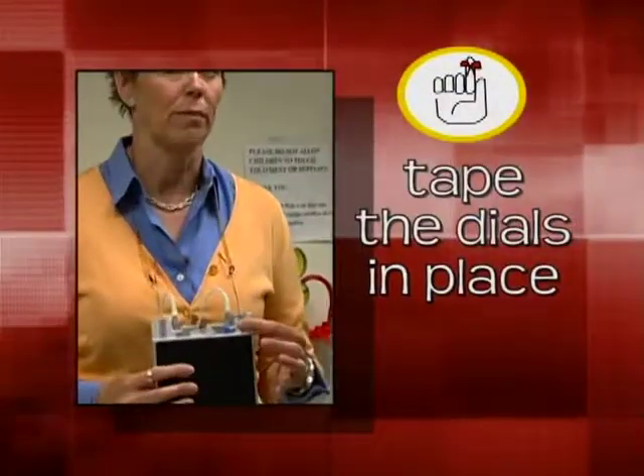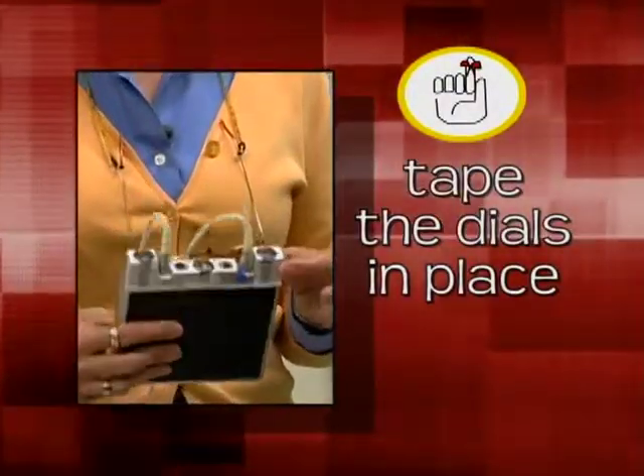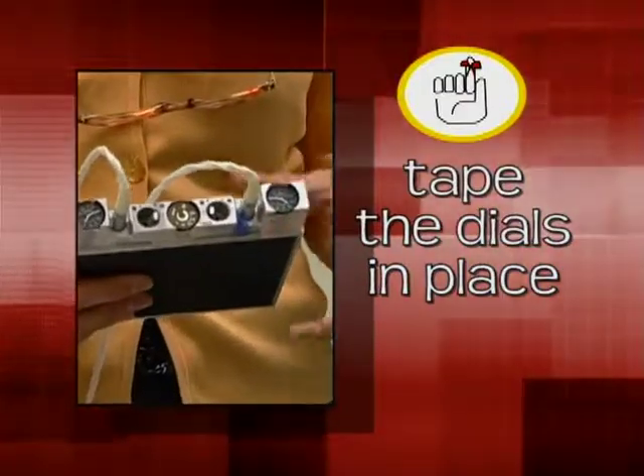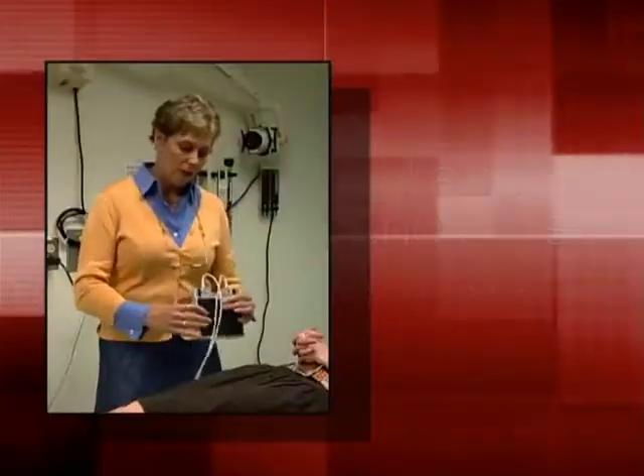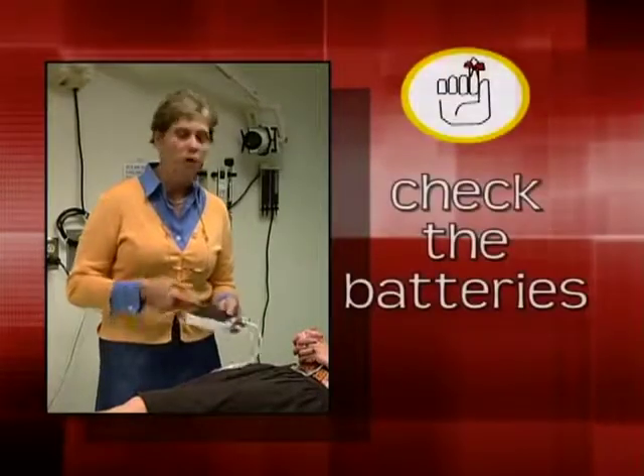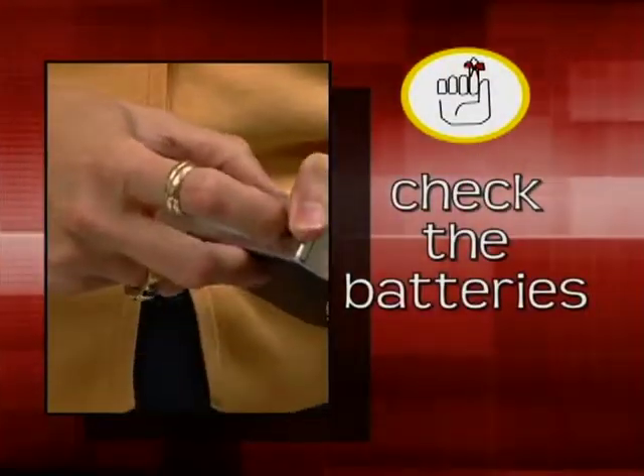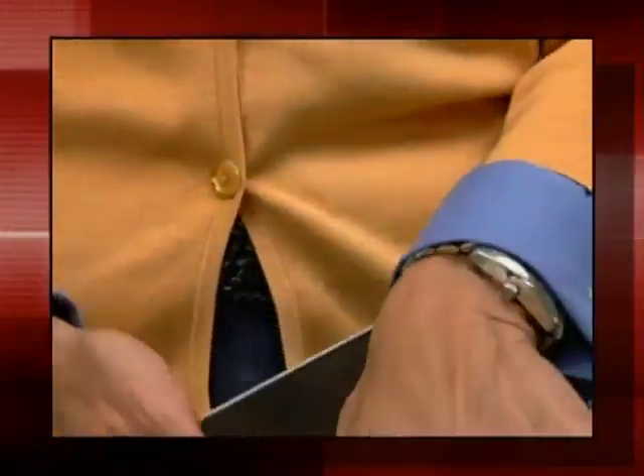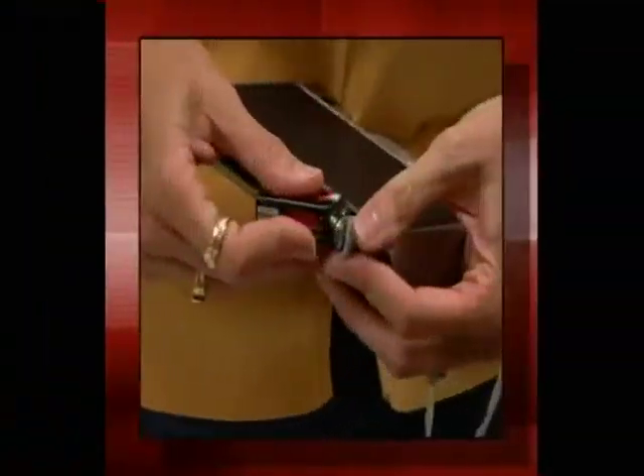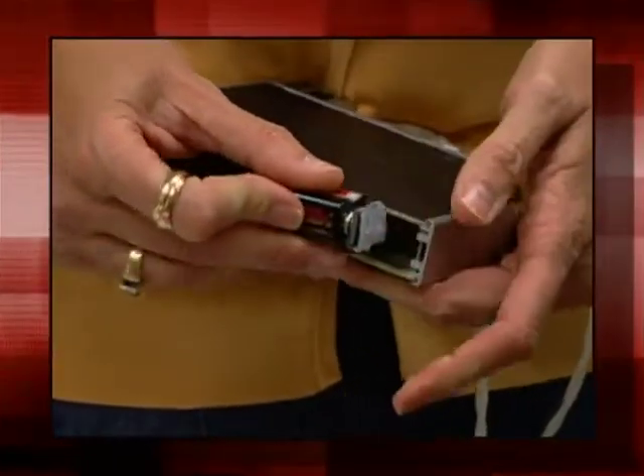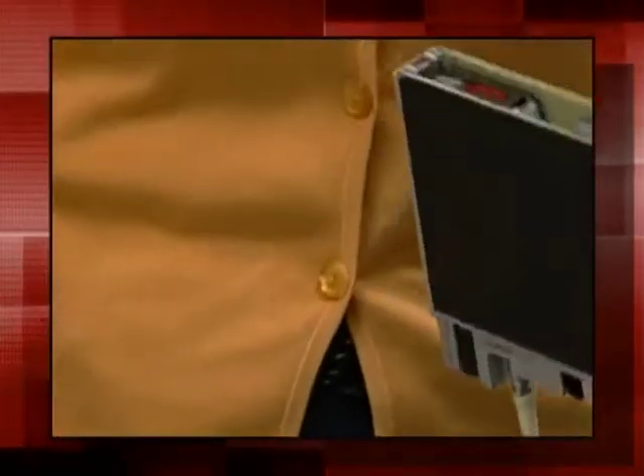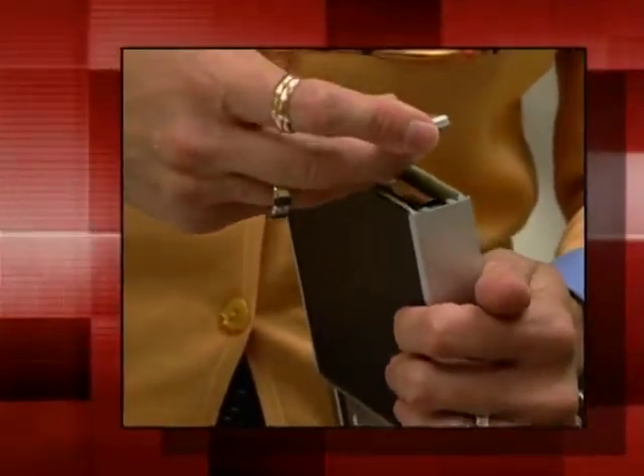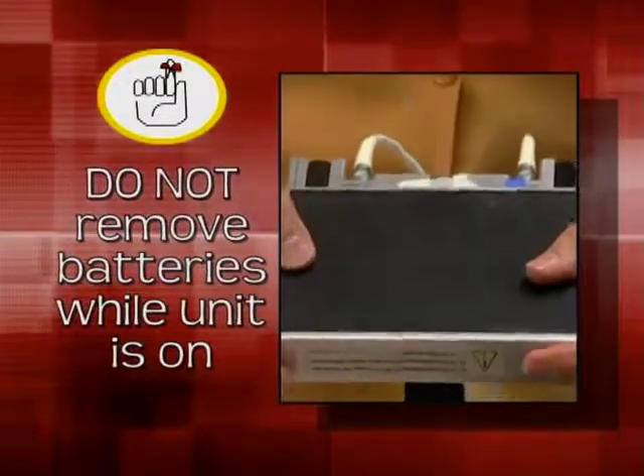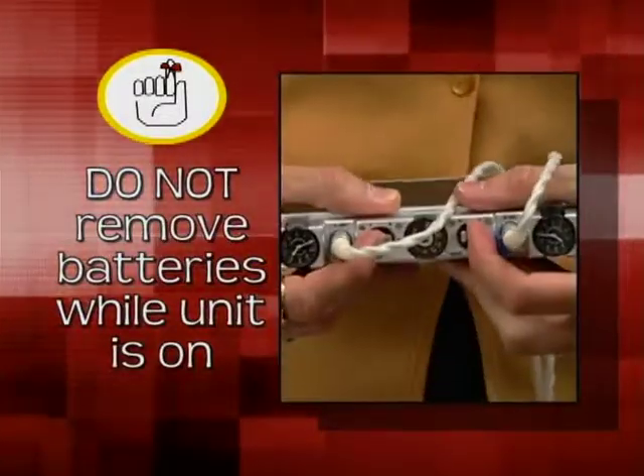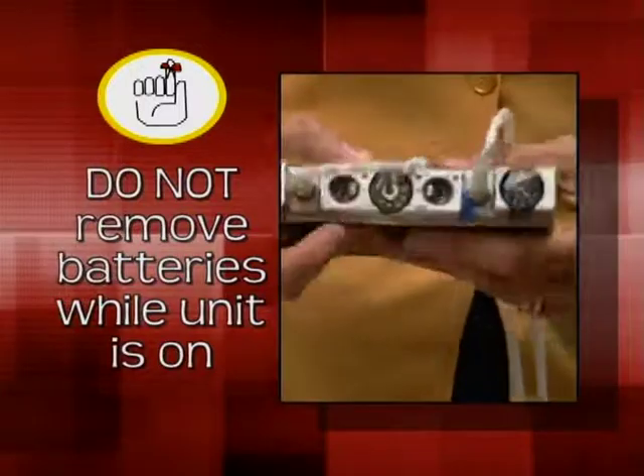Here's a tip to prevent that problem. Simply apply some paper tape across the bottom of the amplitude dials so they can't be accidentally moved. If you look at everything and all the dials seem to be set right, then you'd want to check the batteries. And so the battery compartment is in the bottom of the machine. And so you'll remove the bottom of the device and you'll pop out the batteries and place new batteries in. Okay. Push them back in. Let me put the bottom back on. Never take the battery out if the transmitter is on. It will damage the machine.